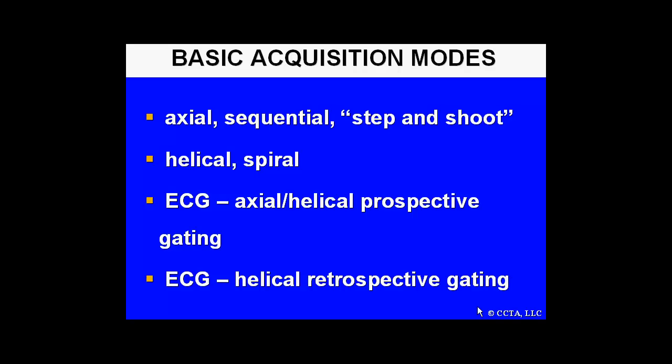There are several basic acquisition modes for imaging using CT: axial, sequential, or step-and-shoot; helical and spiral; and then specifically for cardiac imaging, ECG axial or helical prospective gating, and ECG helical retrospective gating.